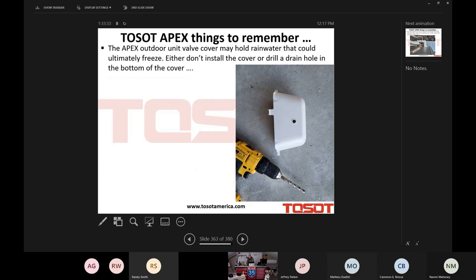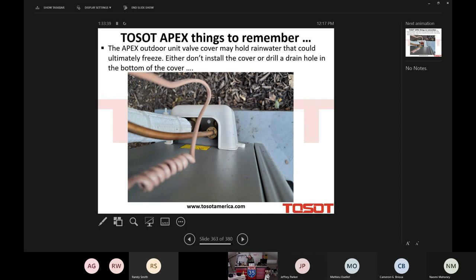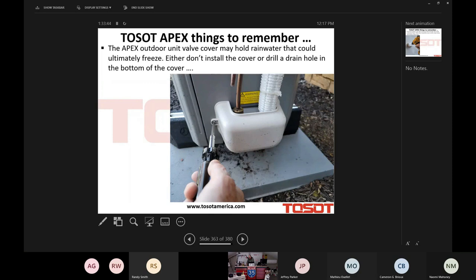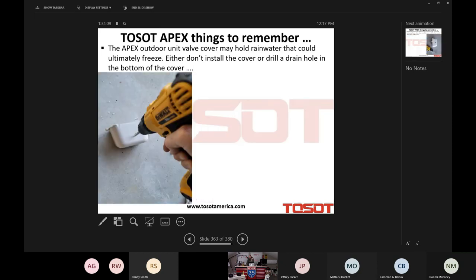No big whoop. We're going to try and have the factory supply that. We're also going to try and have the factory supply a cover that is the same color of the jacket of the outdoor unit. Isn't that obnoxious? It's just something so simple that could have been, that didn't need to be. Give me a gray cover, please. It draws your eye to it because it's a different color than the jacket of the outdoor unit. Hey, look, is it even necessary? No, you don't have to use it at all. But I like it there. I like the fact that the valves are covered, but there should be a drain hole and the color should match. I'm just saying.